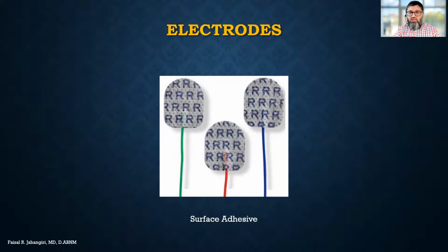So the electrodes, those two electrodes, are used for stimulation. If the electrodes are too far from each other, you are activating a bigger area and you may be activating more than one nerve. So the signal will be huge and good looking, but at the same time you will have a huge stimulation artifact. So if you have a huge stimulation artifact on your screen, that means the distance between your electrodes is too far.